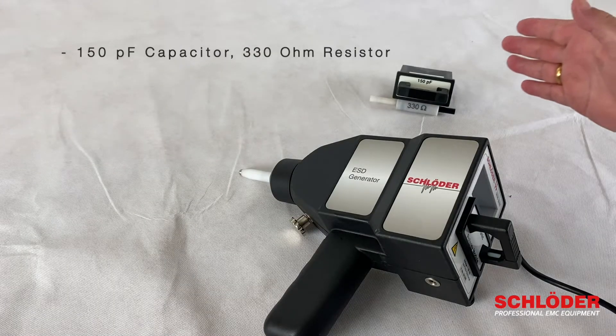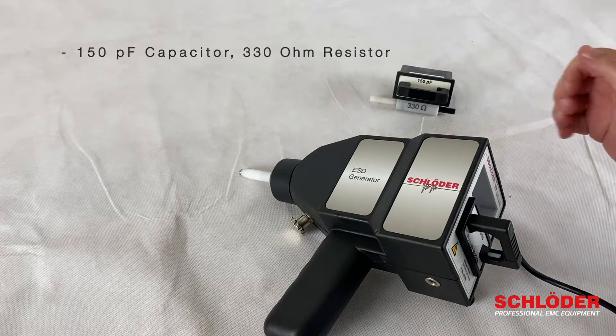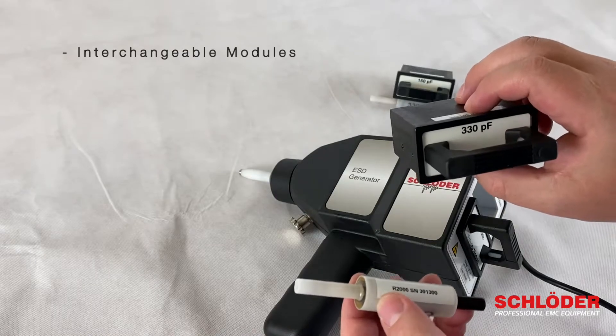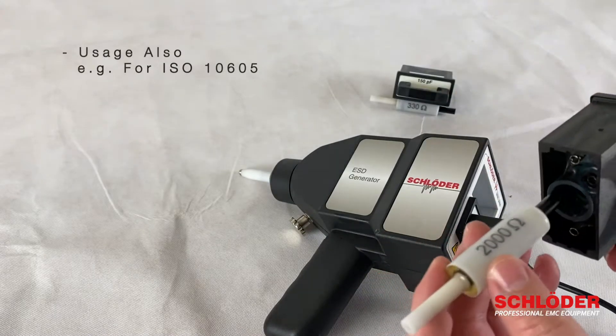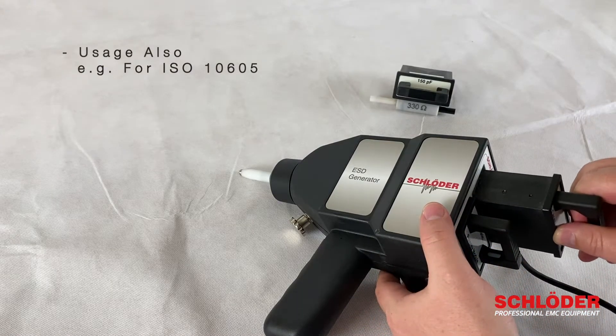The device comes with the standard modules: 150 pF as capacitor and 330 ohm as resistor. The modules are completely interchangeable, so there is a huge variety of possible impedances, which means the device can also be used, for example, for ISO 10605.